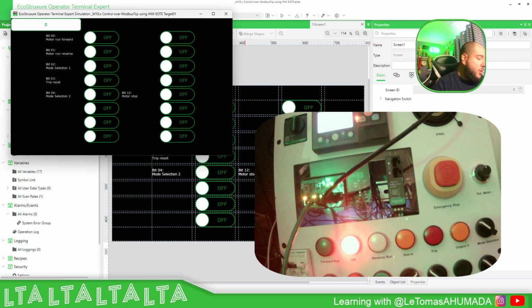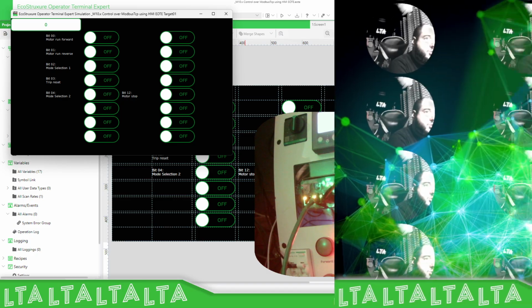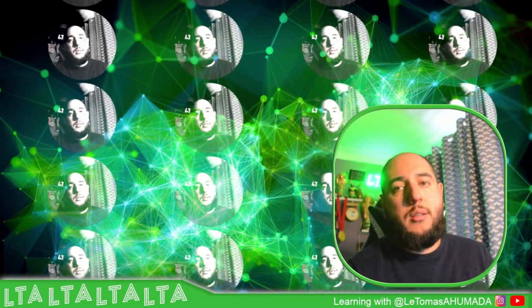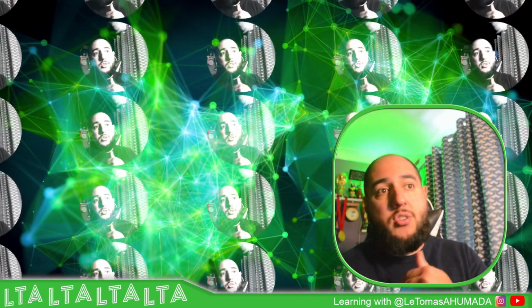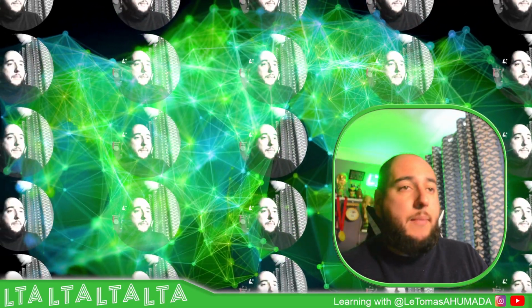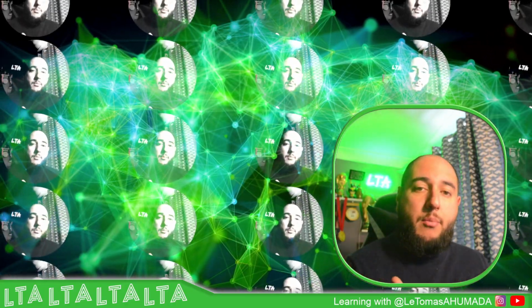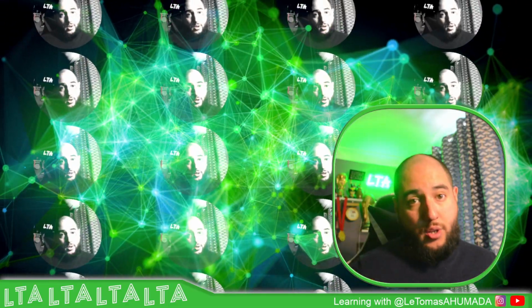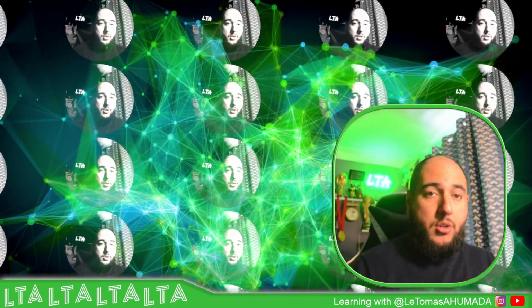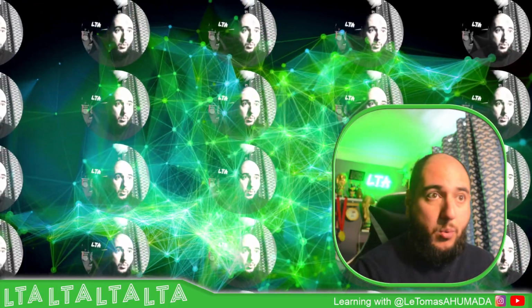So this example is just to show you how you can control, using the operator terminal expert, access information to control the information from the TeSys Tera. Basically it's just on the device, Modbus TCP, and then to the address that you see in the manual on the Modbus on the Ethernet model, just subtract 1 to the address in order to make it work. Okay, and that will do the trick.